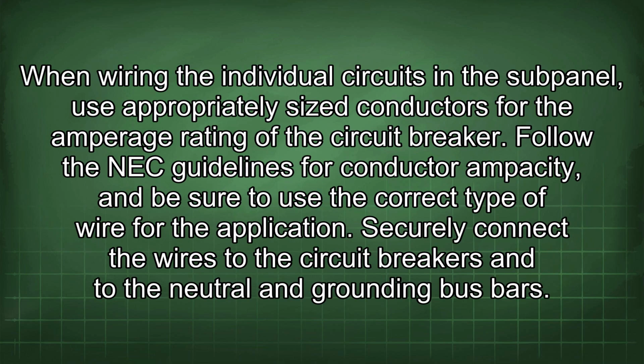When wiring the individual circuits in the subpanel, use appropriately sized conductors for the amperage rating of the circuit breaker. Follow the NEC guidelines for conductor ampacity, and be sure to use the correct type of wire for the application. Securely connect the wires to the circuit breakers and to the neutral and grounding bus bars.